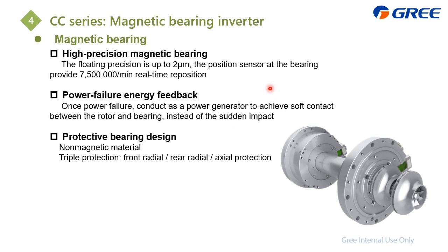This is the magnetic bearing, and this is the sample picture. This is the two-stage impeller, and this one is the shaft. This one is the bearing. It just generates the magnet to suspend this shaft. And there are 3 main features of it. First is the high precision. The floating precision can be up to 2 μm. First we need to do its positioning. There is a position sensor which can provide the bearing RPM and position in real time.